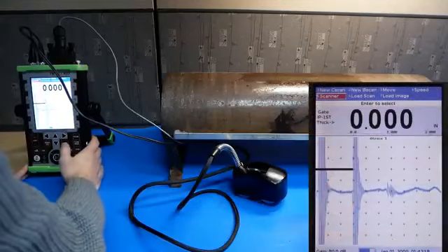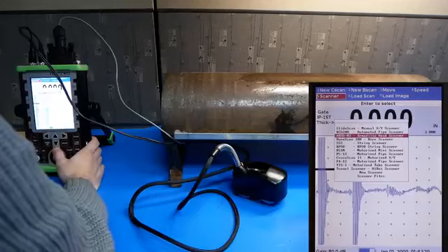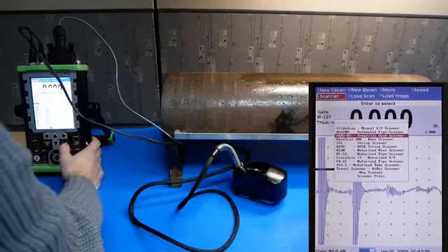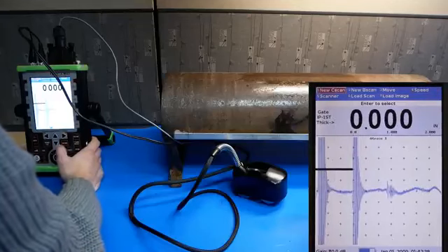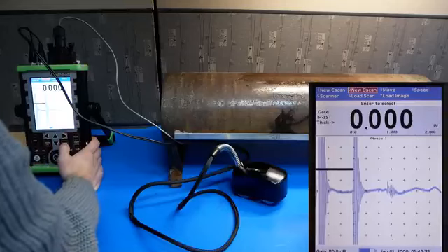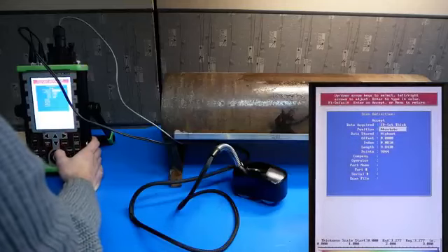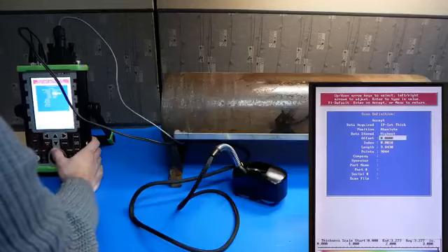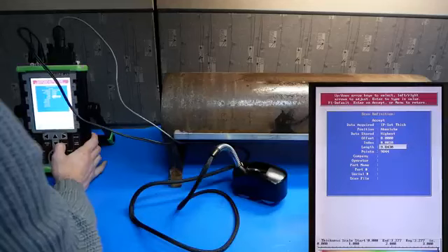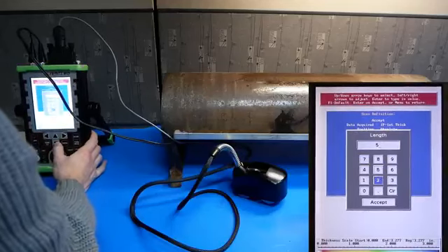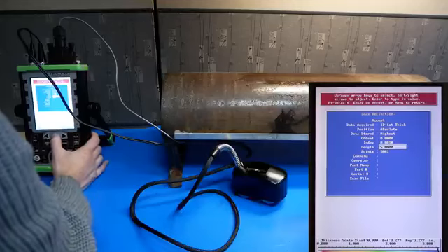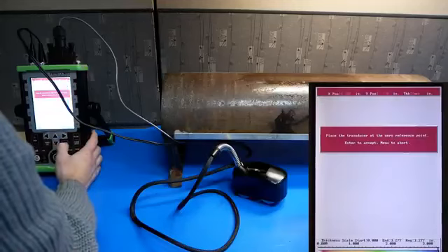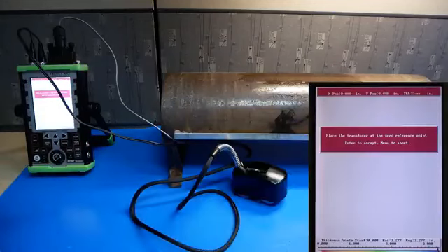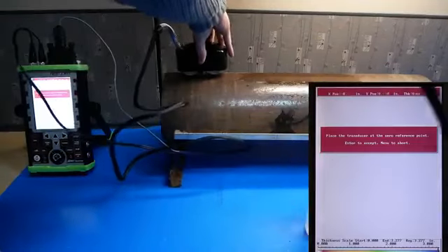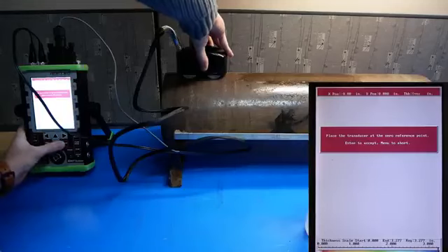Next, go to Scanner on your Raptor. Select AEHS-03 for the Armadillo hand scanner. Go to New C-Scan or B-Scan. We'll do a B-Scan in this case. And select the range of measurement. We'll change this to 5 inches. Couple the probe to the test piece and place it at your starting point. Push Enter when you're ready.